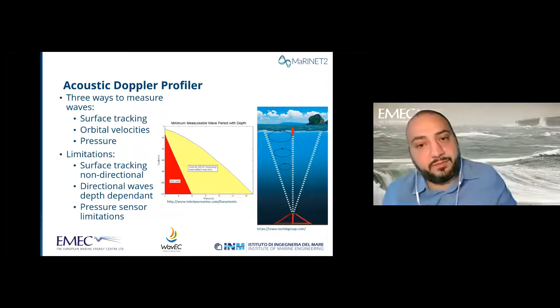To get directional data, you would need to use the orbital velocities measured from slant beams as well. And the problem in that case is that the acoustic footprint of those beams diverge quite a lot the deeper you go, right? Because they're at an angle. So if your ADCP is deployed quite deep, the distance between the two beams will be quite wide at the surface. And to do the directional analysis, you need the data from all the beams. So the smallest wave that the ADCP could detect has to fit into that acoustic footprint at the surface. Any wave smaller than the distance between the footprints won't be detected by the ADCP.